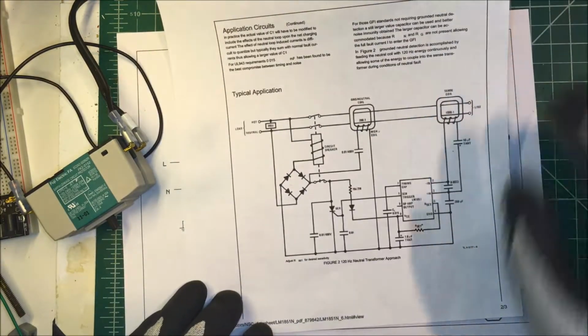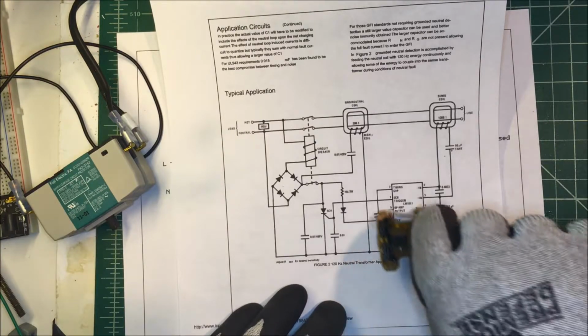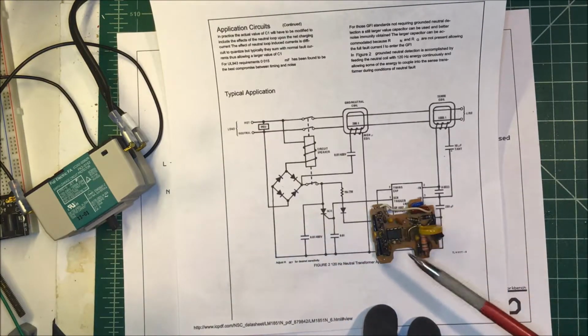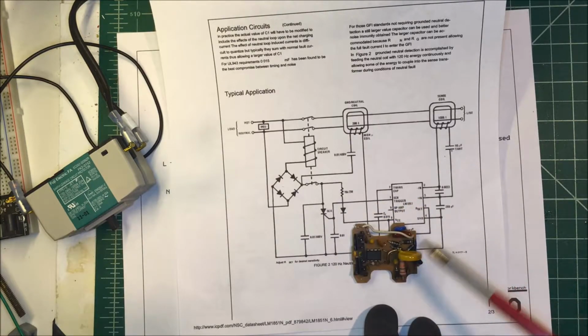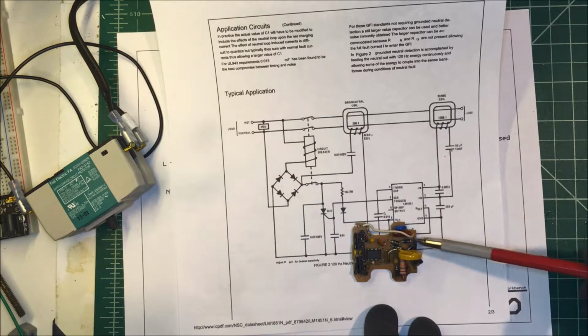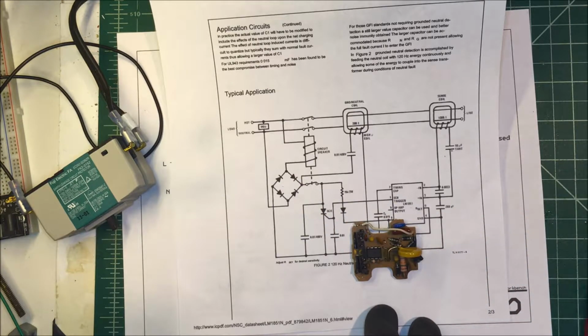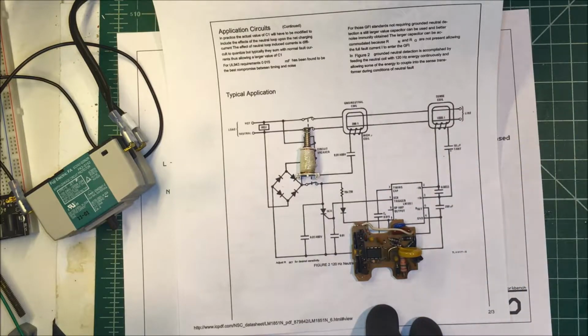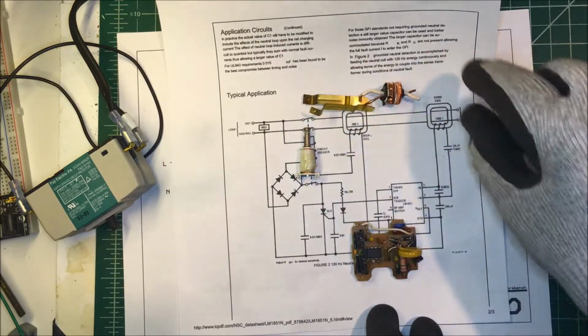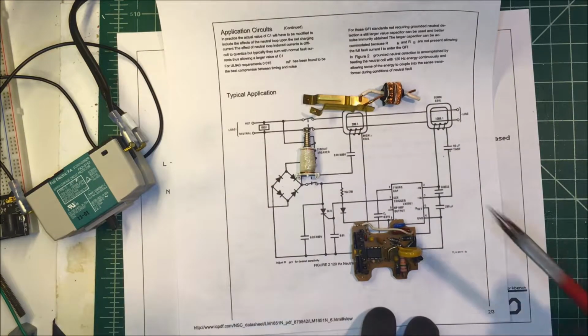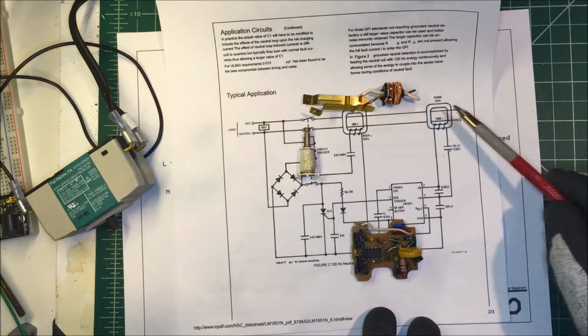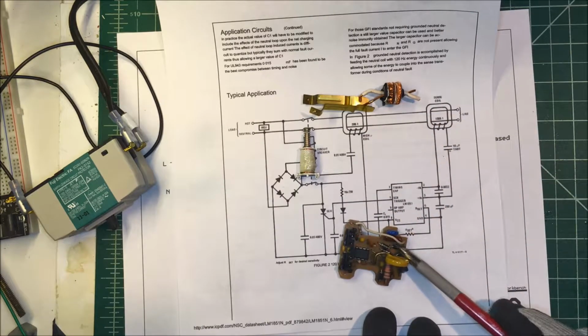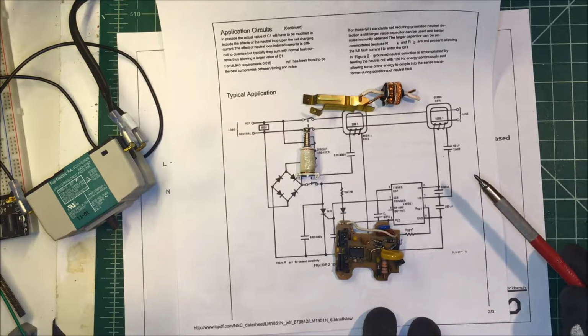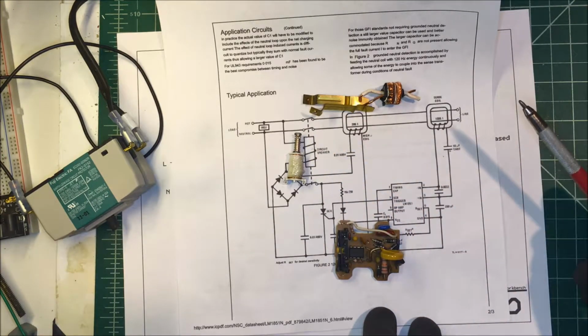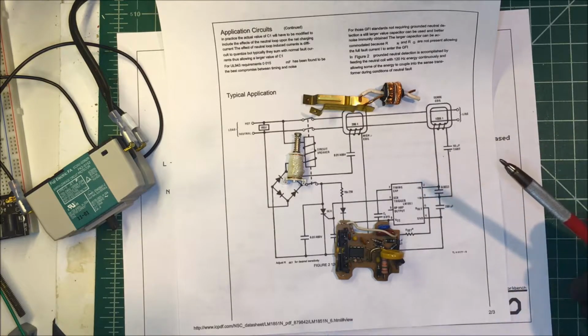and I actually have the diagram of that circuit here. So this is how it's set up. This is an actual one out of a ground fault interrupter. This is your LM1851 here. Your little bridge rectifiers over here. Now the coils right like that, and then you have your set of contacts and your two coils there. One coil here is actually tied to the neutral, and the other is your sense coil here, and they operate through this LM1851 here, tripping the relay out here. So that's how that GFI works.